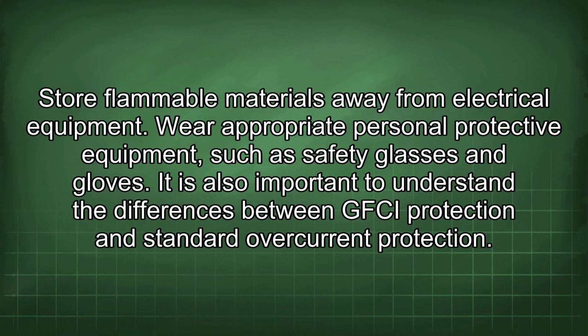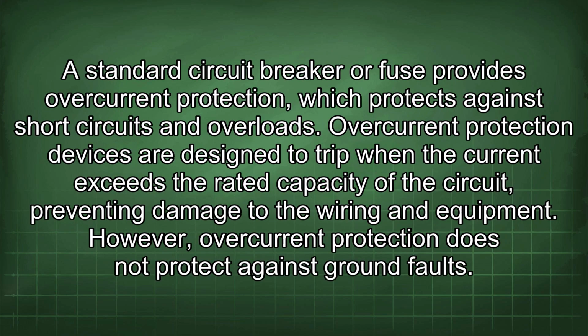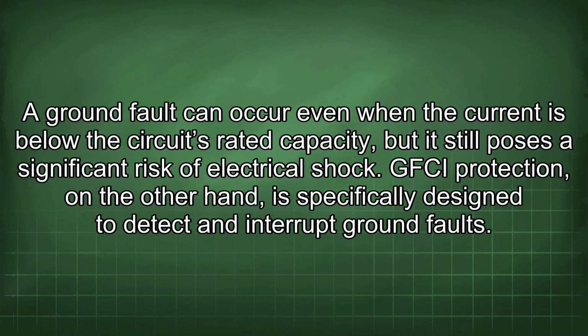It is also important to understand the differences between GFCI protection and standard overcurrent protection. A standard circuit breaker or fuse provides overcurrent protection, which protects against short circuits and overloads. Overcurrent protection devices are designed to trip when the current exceeds the rated capacity of the circuit, preventing damage to the wiring and equipment. However, overcurrent protection does not protect against ground faults. A ground fault can occur even when the current is below the circuit's rated capacity, but it still poses a significant risk of electrical shock.